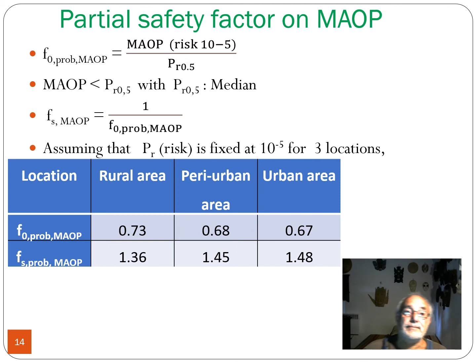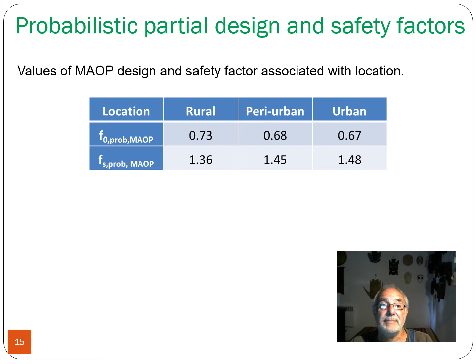Remember that the safety factor is the inverse of the design factor. If you consider the probability of risk fixed at 10 to minus 5, you can get the value of the MAOP for three locations: rural area, peri-urban, and urban. The results of the computation of the probabilistic partial design and safety factors are given in the following table. You can see that according to the locations, the design factor is in the range 0.73 to 0.67, and the safety factor in the range 1.36 to 1.48.